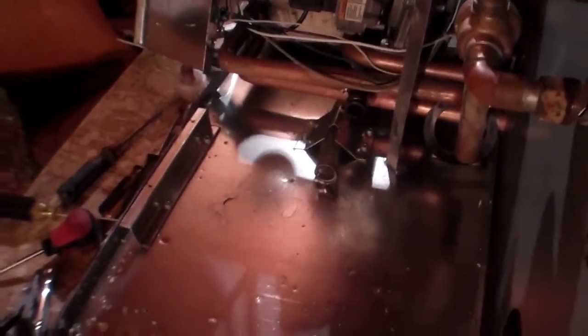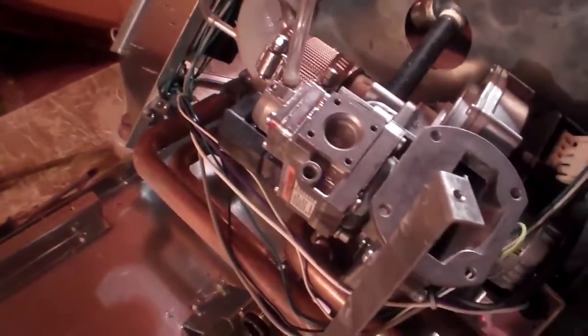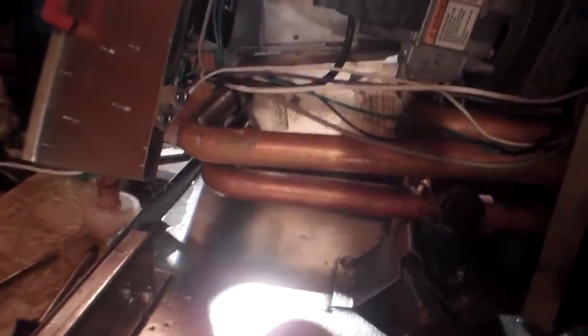So now as you can see, we've got the old heat exchanger out. And I'm going to go through and do a little detailing on the wiring and get everything tied back up where it needs to be. This would be a good time to get in here and really inspect everything. Take a look at your structure and make sure you don't have any cracks or breaks in anything. Take a look at your bottom exchanger there. Make sure there's nothing broken, nothing loose. And we've got our old exchanger here.